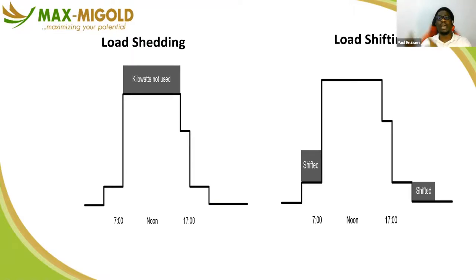Why don't you use another kind of automation that schedules those operations? For example, I know my overhead tank is 3,000 liters, and all of us in the building during the peak of 11 and 5 will not use up that 3,000 liters. Water should pump by 10 and pump again by 5. I use another kind of automation — not a level-demand pump, but a time-based automation. So by 5, I know my tank is going to fill up. By 11, I know my tank is going to fill up, so I can cover my peak and make sure my pump does not come on during my peak.